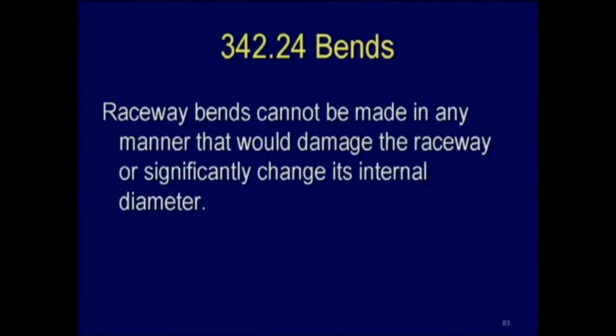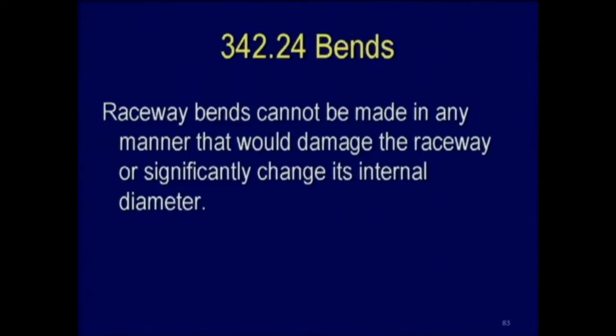342.24. Raceway bends cannot be made in any manner that would damage the raceway or significantly change its internal diameter. This rule about bending in .24 on all the metal raceways has the same thing. So I'm not going to be saying this and reviewing this on all the other raceways. A lot of these rules are repetitive as we go along, and I'm just going to quickly run through. What it's saying is that you cannot kink the raceway. You use the proper tool, you should be fine.